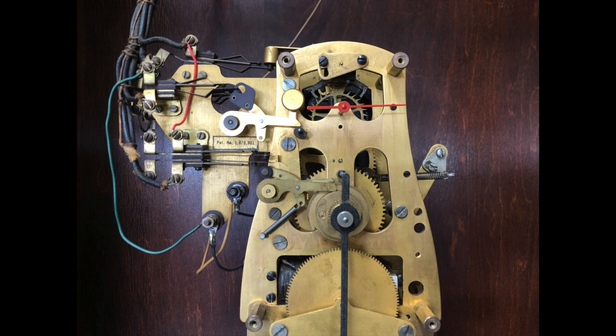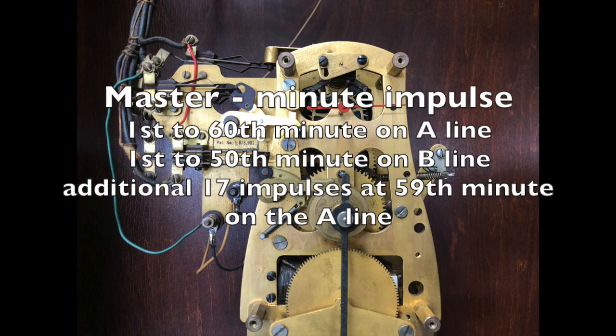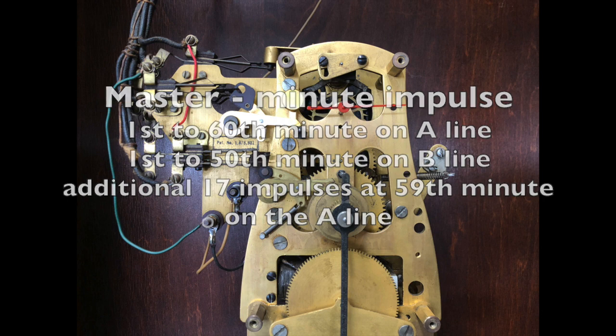The master movement correction contacts are wired to transmit a minute impulse on the A line from the first to the 60th minute and also a minute impulse on the B line from the first to the 50th minute and an additional 17 impulses on the 59th minute via the A line.